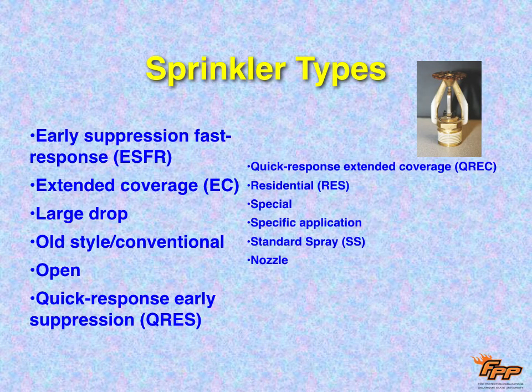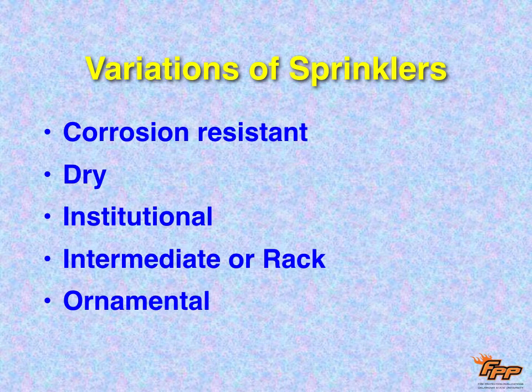There's lots of different sprinkler types. The main ones you're going to see are uprights and pendants. There's a kind called early suppression, fast response, extended coverages. There's larger drops. There's old style. There's open style. We've talked about a lot of the different kinds, but here, let's look at some different variations. There's corrosion resistant, there's dry institutional, there's even sprinkler heads that are used in the racks of storage places, and then there's ornamental kinds that are made to look nice.